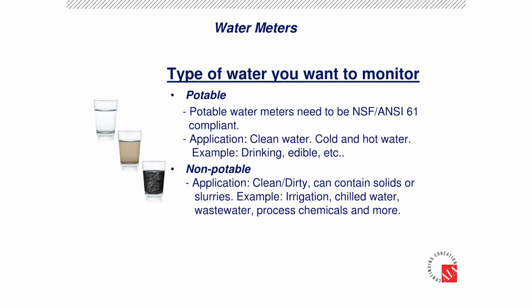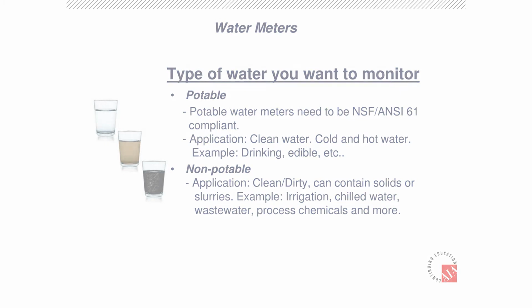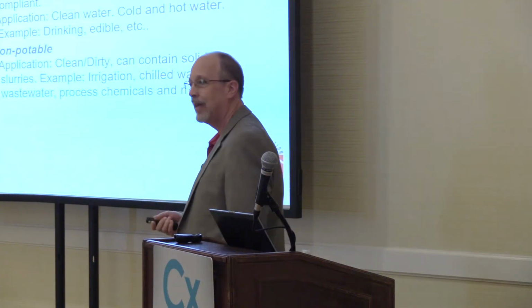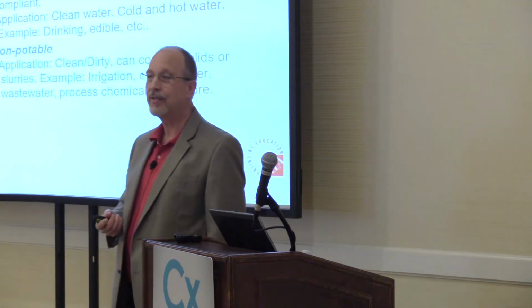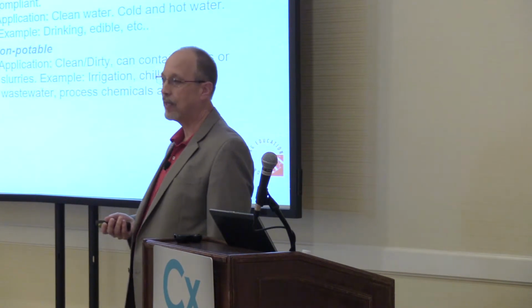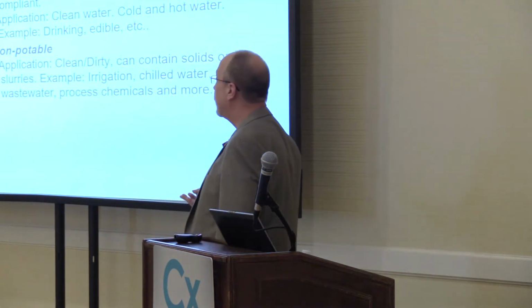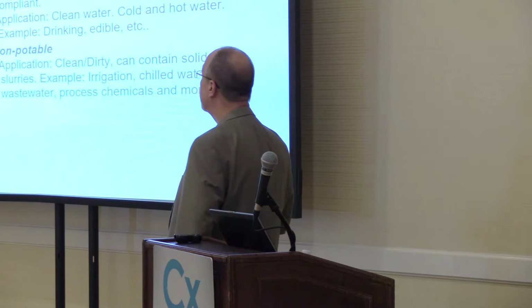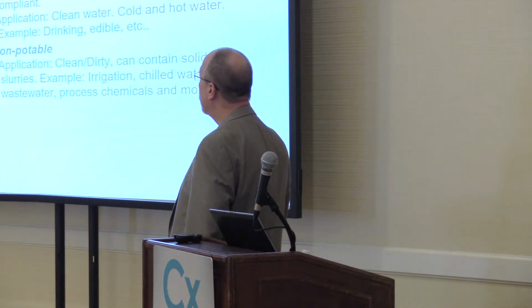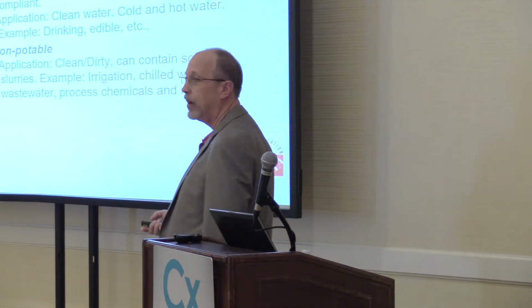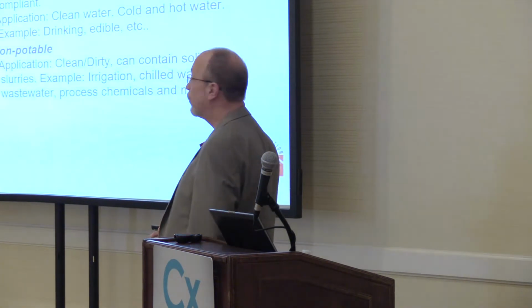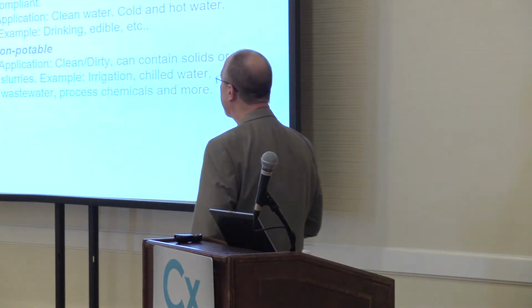Now as far as an ultrasonic flow meter, you're saying, well, I can look at this, this looks like it's potable water. Well, you've been in Florida here today. Sometimes you can see potable water looks like this. Opaqueness has nothing to do with it. Opaqueness is just dissolved suspended solids. There's nothing floating in there. It's just the colorization of the water. Now over here, this is what we call a slurry. This is a cup of mud. And a cup of mud is not really going to be very good for your particular application.